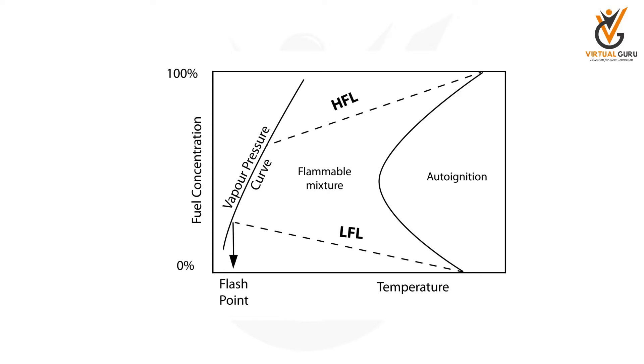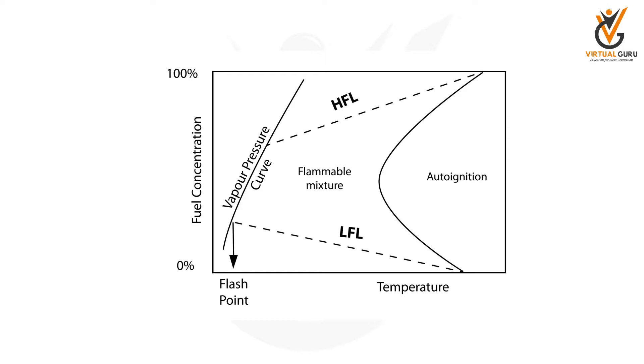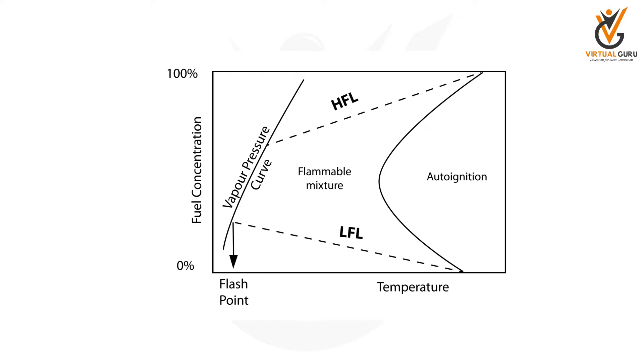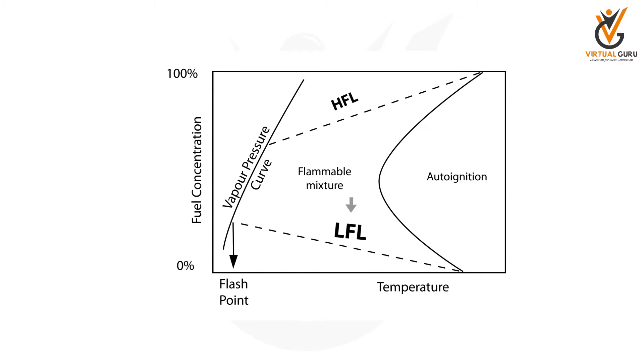Now let us discuss the vital property. We all know that there should be a mixture of fuel and air — in that condition any spark can ignite. This mixture, which we can call vapor in air or gas in air, must be at the right concentration for fire to catch. The lowest concentration at which it can catch fire is called the Lower Flammable Limit, and the highest concentration where it can catch fire is called the Higher Flammable Limit.